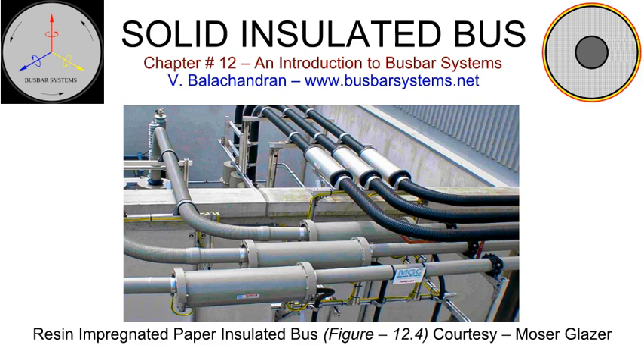The solid insulated bus comprises four major sub-assemblies: insulated conductor with bends, site joints assembly, end termination, and support system. Insulated conductor with bends. A solid insulated bus connection is designed to have the least number of site joint assembly.